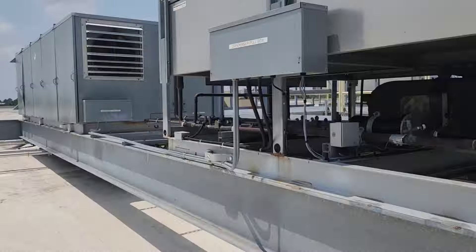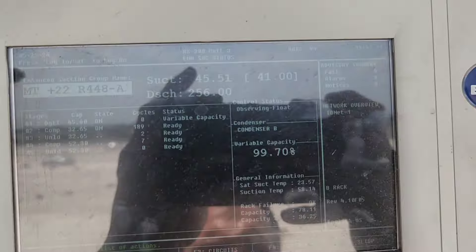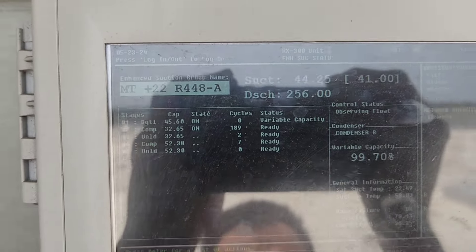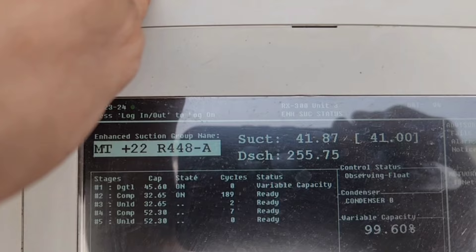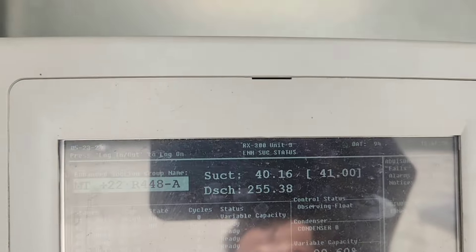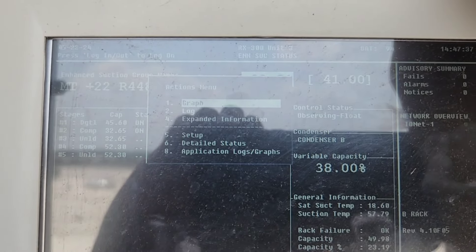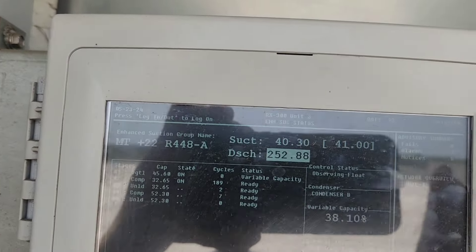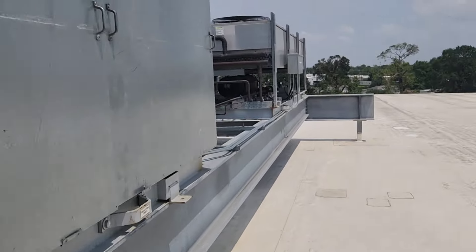Let's go look at the other rack. Here our second stage just came on, and it's pulling the suction pressure down. This one's looking much better — 30s, 40s, and some 50s. The discharge is a little high because we've got one bad condenser fan motor, and that's why it's running at 100% — it can't pull that pressure back down.